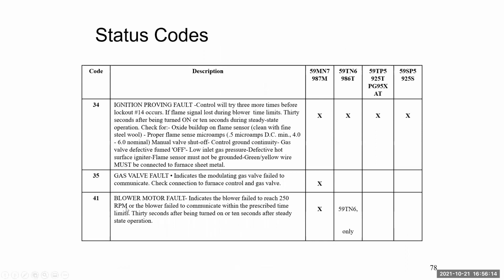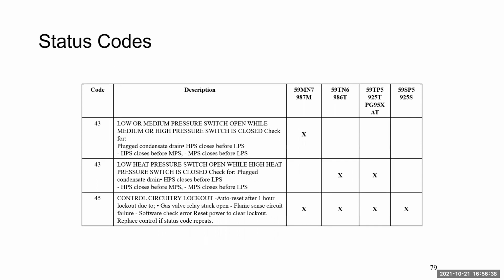Right, there's that code 41 I talked about earlier on that motor blower fault. It's basically telling you that your motor failed to reach its RPMs. Only a couple of models you're going to find that in, and that's the 59MN7 and the 987M, and then the 59TN6. But again, your furnace will have all these fault codes that are related to that specific furnace you're working on.